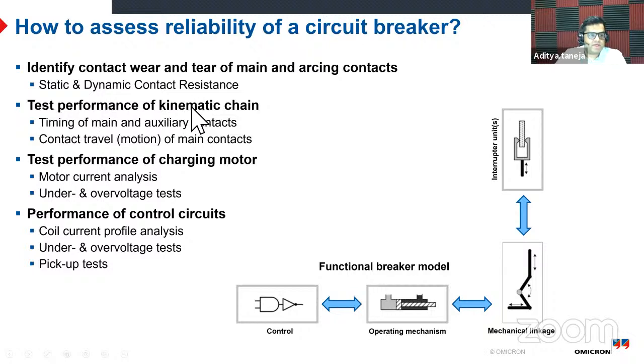Then for performance of the kinematic chain, the mechanical part, if it is working properly, there has to be some distance which it is moving, and it is doing that in a certain period of time. So distance and time are the main criteria for checking the performance of this mechanical part. So we do timing tests, and also we should do a travel test. Both of them together will give you a clear picture if something is not working properly, like dampers, or if something is worn out, or if there is any slack. You will see it here.